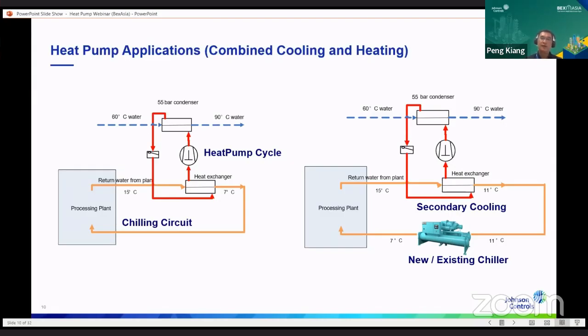The one on the right-hand side is a very practical experience from some plants, where you may have an existing plant which is already doing cooling, and you also have a boiler at the same time doing heating, which is separate, right? So how do we link them together? By tapping or pre-cooling some of this cooling energy from the plant before it goes to the existing chillers, and utilizing this pre-cooling to generate hot water on the other side at the condensers.